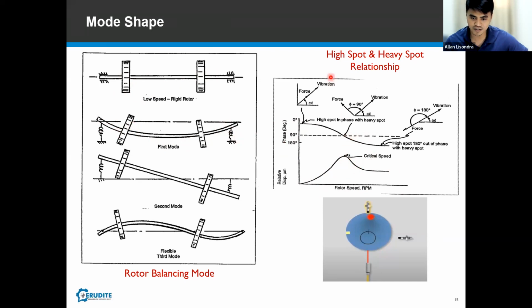As you can see, there's also a relationship between high spot and heavy spot. At rigid, or at this point, the high spot and heavy spot are on the same position or location. That's why some people do the balancing first at low speed, because normally the high spot and heavy spot are at the same position.